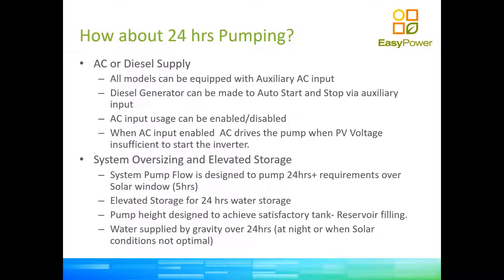Depending on your application, it can be better to oversize your system to pump water to an elevated reservoir. Domestic applications may be difficult because to achieve three bars you need a significantly high tank. But for commercial and agricultural applications, this is very workable. A difference in terrain height of 40 meters is easy to achieve in some parts of the country, and this is where you want your reservoir — giving you three bars of pressure at the off-take point.